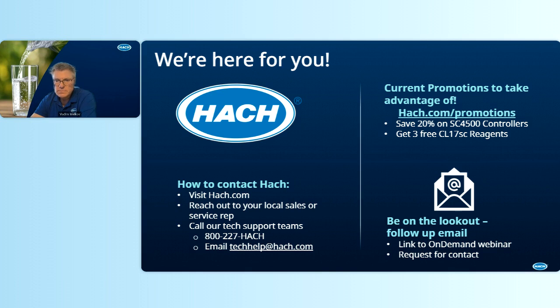Next question is, what is the pH range for mono-, di-, and trichloramines? That's a great question, and I know Terry can answer that question. I'll kick it off. So the ideal range to maintain monochloramine as the target disinfectant is above 8, like 8.2, sometimes between 8 and 8.5. This is the ideal range to maintain a stable concentration of monochloramine. If the pH goes lower, below 8, then the equilibrium changes toward dichloramine, and you have your taste and odor issues. Terry, you can add.